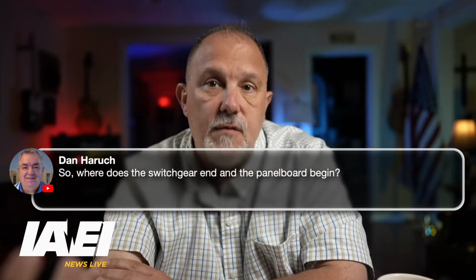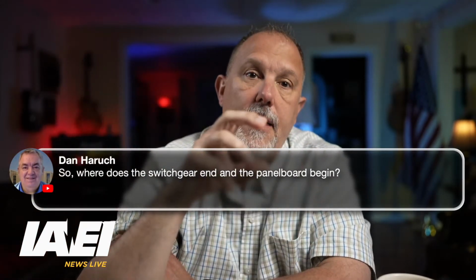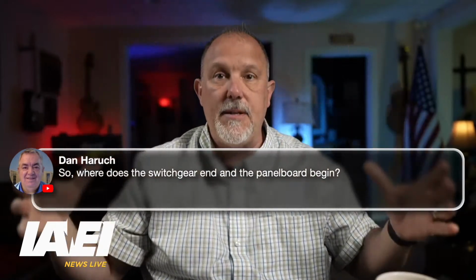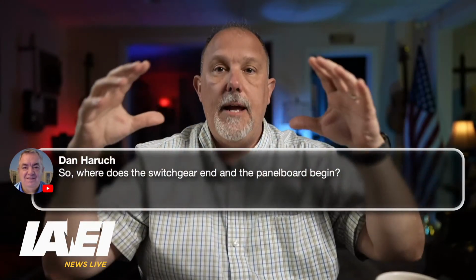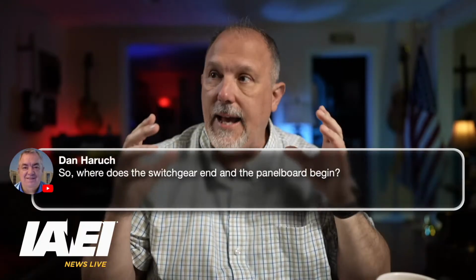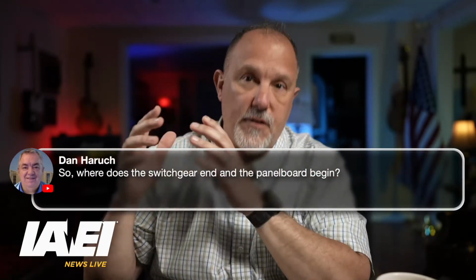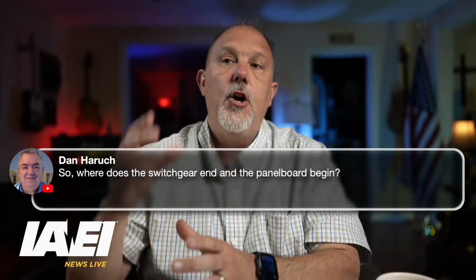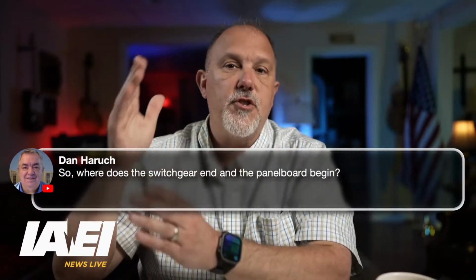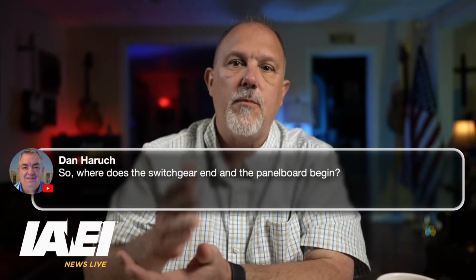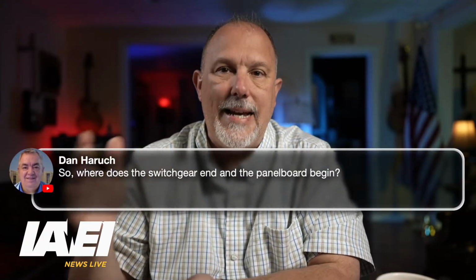But if a transformer is in the switchboard, the entire assembly is a switchboard, and it's listed to UL 891 for switchboards. But that doesn't mean a transformer is not a transformer, right? And a transformer will have to be evaluated to its standards.